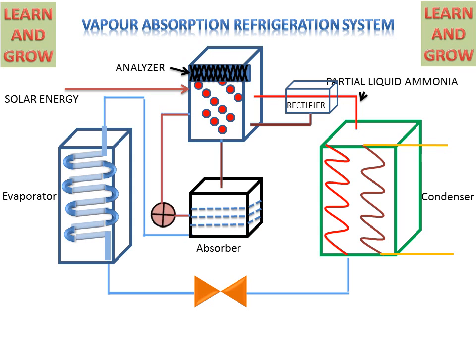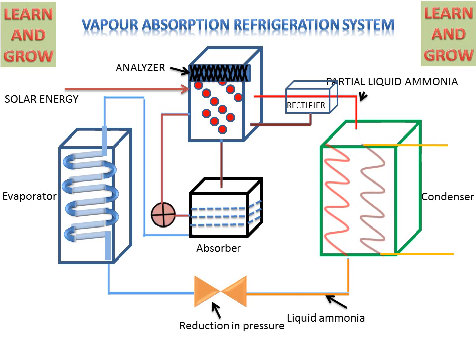This partially liquid Ammonia goes to the Condenser and is converted into fully liquid form. This liquid Ammonia then passes through the Expansion Valve, where pressure and temperature are reduced. It then reaches the Evaporator, where it absorbs the heat of the space and converts into low-pressure vapor. This low-pressure vapor then goes to the Absorber. Through the Evaporator, the space that we want to cool is cooled.